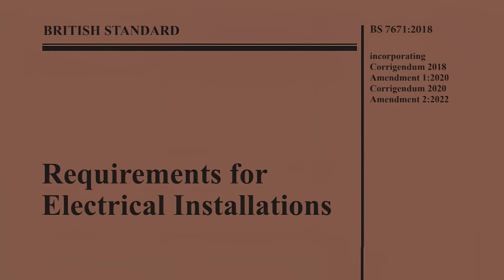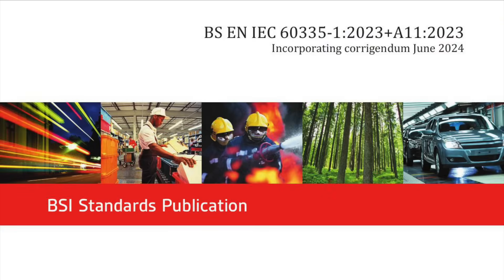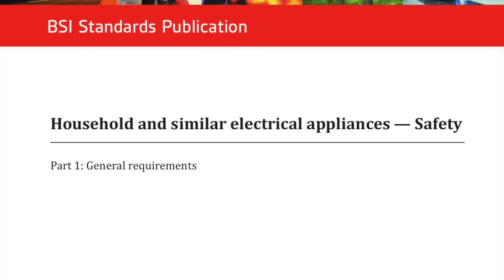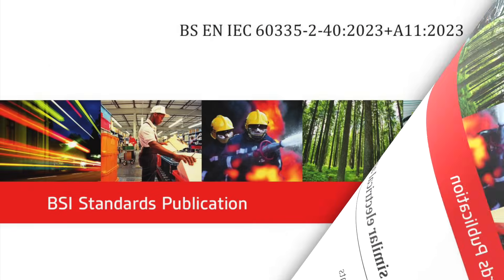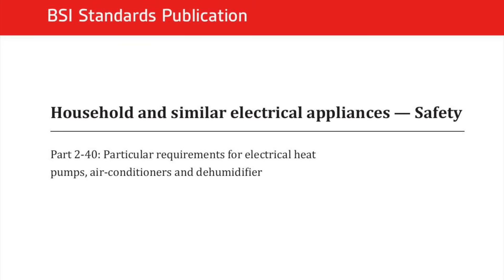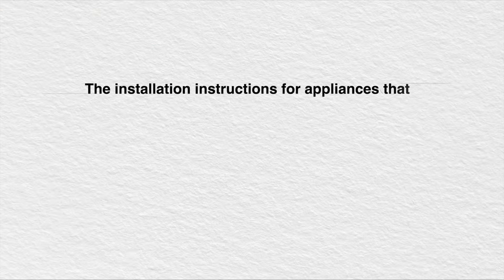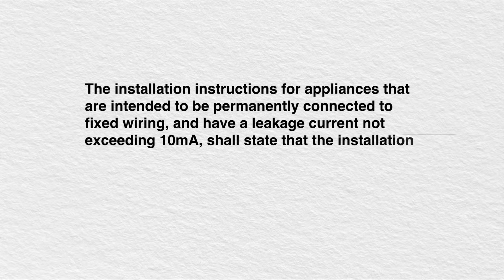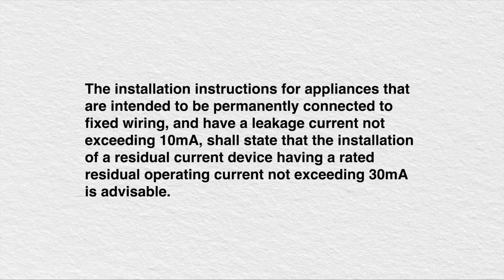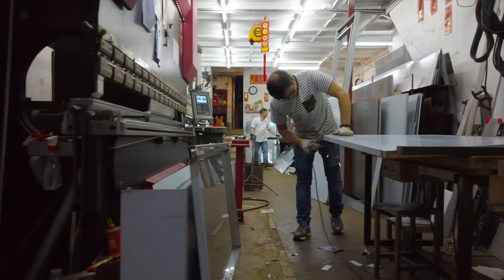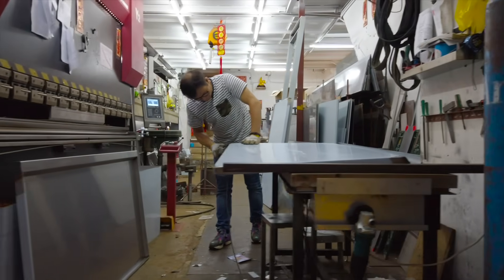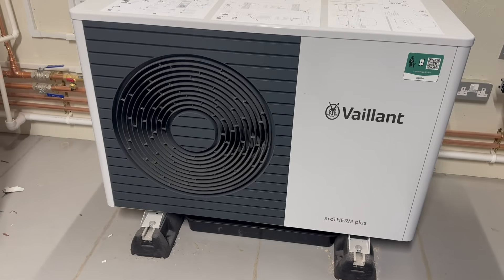But there's more to heat pumps than just BS7671. BSEN IEC 60335 is a safety standard relating to household and similar electrical appliances, and part 2-40 of this document covers specific requirements for heat pumps. Within that document, we find this direction: the installation instructions for appliances that are intended to be permanently connected to fixed wiring and have a leakage current not exceeding 10 milliamps shall state that the installation of a residual current device having a rated residual operating current not exceeding 30 milliamps is advisable. So while this direction is aimed at manufacturers and not electricians, the heat pump makers will want to comply and therefore should recommend in their instructions that an RCD is used to protect the appliance.